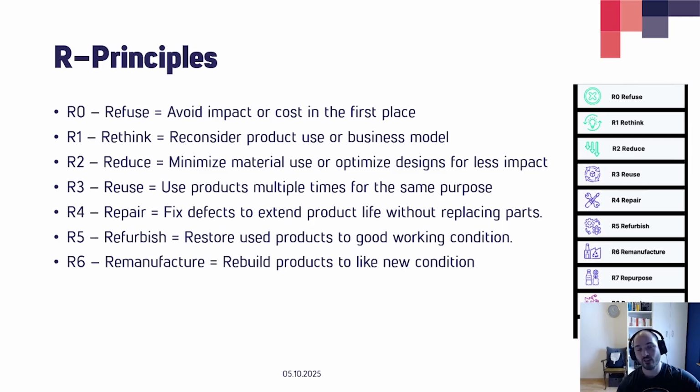But remanufacturing would be such a case when you have a catheter that you used once, they get collected, certain companies wash them, clean them, maybe sometimes repair them, test them, and become the legal manufacturer of that medical device, no matter what's printed on there. So you may have an original device manufacturer that brought the device on the market the first time, and then it gets used in the hospital, gets picked up by another company, reprocessed, and they are now the legal manufacturer of this medical device. That is what remanufacturing would be.